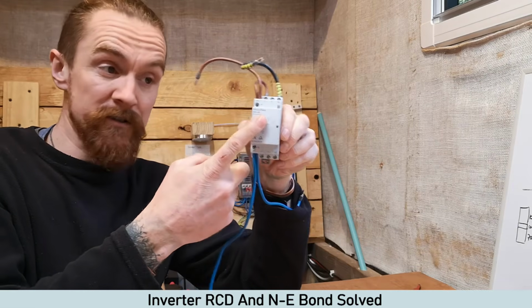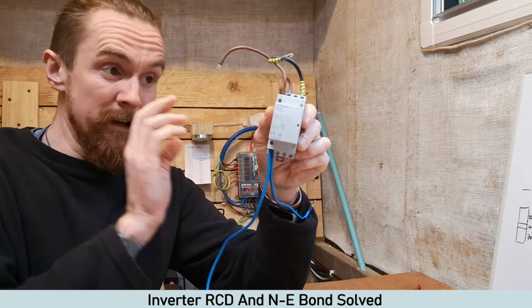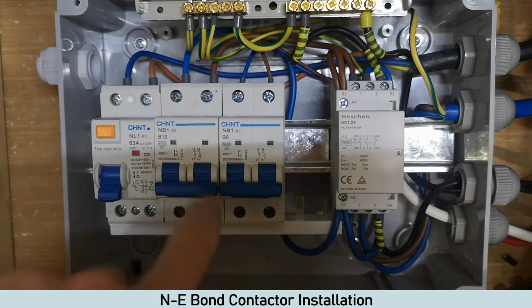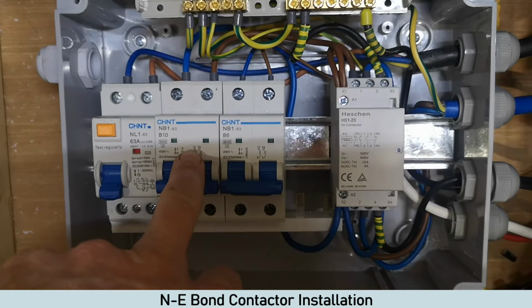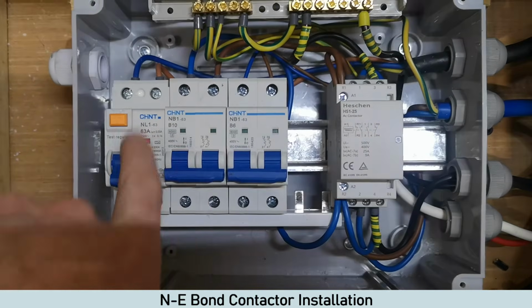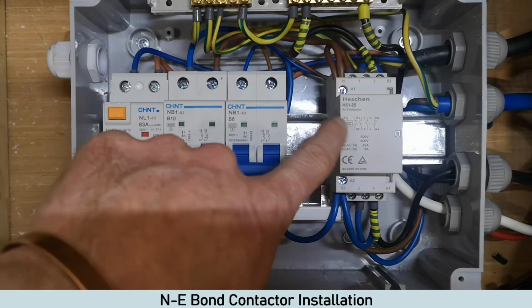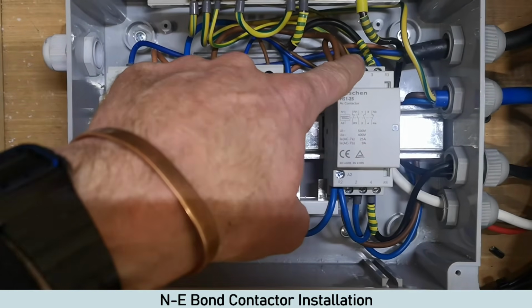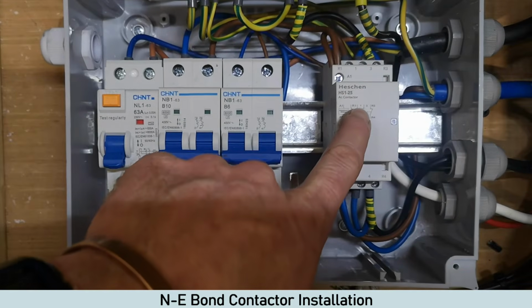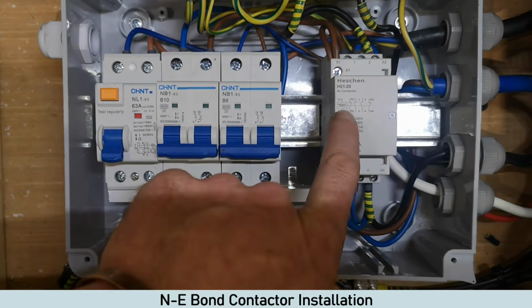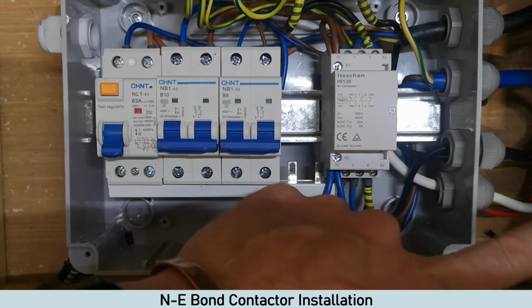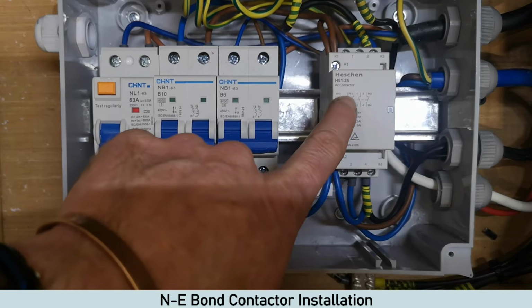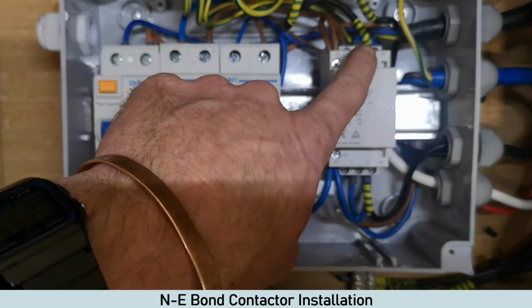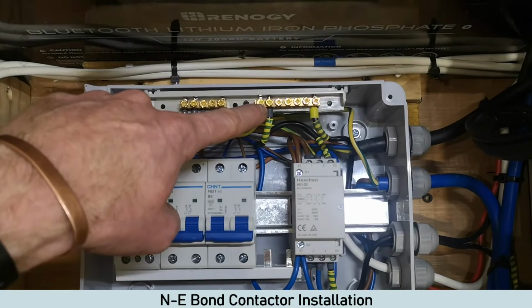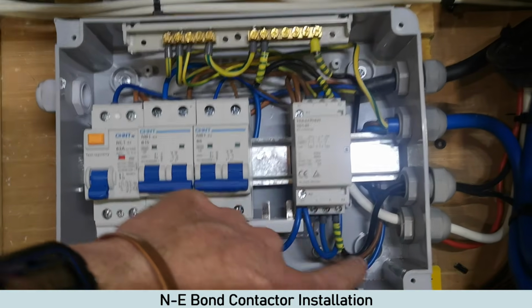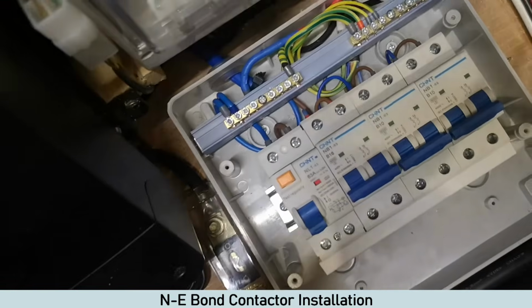That's what this does. So I'm actually going to show you how to wire this now and how to install it. I've installed it into DB1 because it's going to be fed off this circuit breaker, which was feeding the inverter charger. So obviously when that's turned on, the coil energizes. The power coming out of it also goes into the top of the contactor, which is into 1 and 3, so live and neutral. And then live and neutral come out of 2 and 4 into the inverter charger. The other connection we've got is the end one, the normally closed one. So we've got one going from the earth bus bar, and then the other end goes all the way around and links to the neutral.